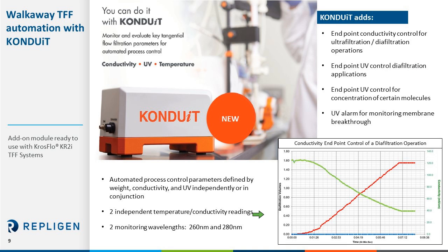Now, we have just heard about the KR2i and its ability to automate your TFF process based on pressures and weights. We're now very excited to add the KONDUiT to our suite of system components. KONDUiT is an add-on module ready to use with new and previously installed KR2i systems. The KONDUiT supports real-time monitoring and endpoint control of solution conductivity, UV, and temperature for TFF operations.